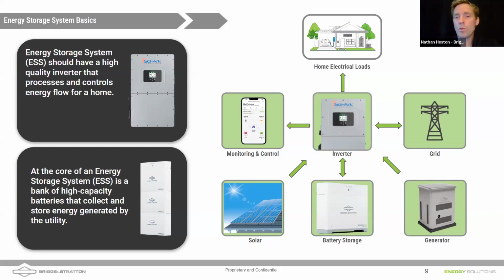But having an all-in-one inverter certainly simplifies the installation process. Now, the inverter that's shown on that screen is capable of managing different power sources. And so if the grid goes down, that inverter is capable of taking power from solar to cover the loads, and if there's excess power, to charge the batteries. And then if that solar power is no longer available, and the grid's still not available, it uses that battery power to cover the home's electrical loads.